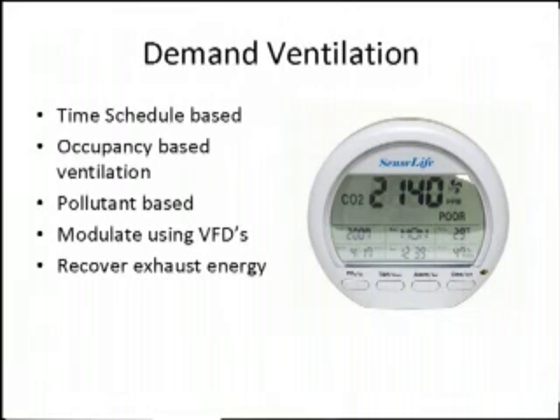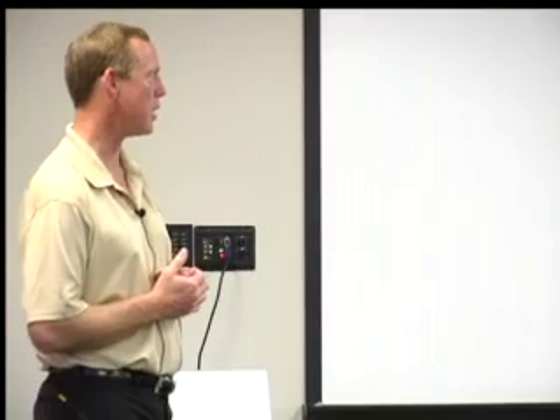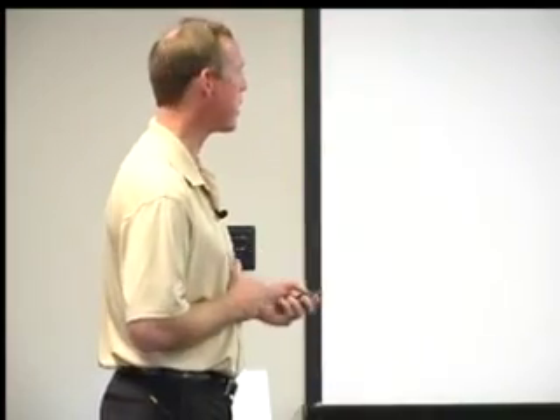Finally, recovery of the exhaust energy. So when we're running these buildings, every air that comes in, or as we add ventilation air, we have to take air out at pretty much the same rate. So the idea here is trying to recover some of that energy because we're pumping out that 70-degree air out of the space. We've spent a lot of money to get to 70 degrees. We want to try to recover some of that, and I'm going to show a little bit of that technology.